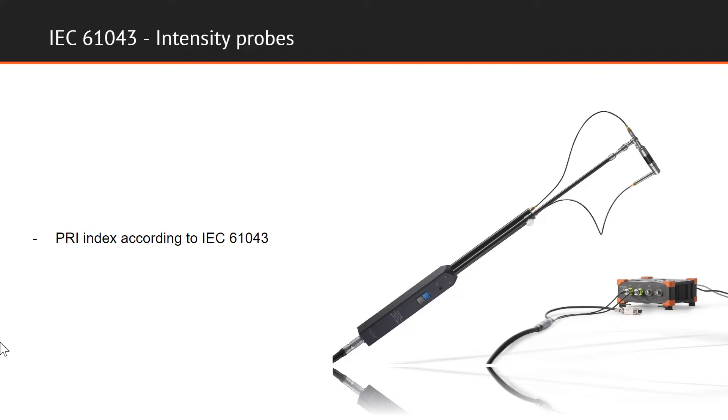In addition to sensitivity measurement and phase check, the pressure residual intensity index for the complete system is also calibrated, in accordance with the demand stated in IEC 61043.